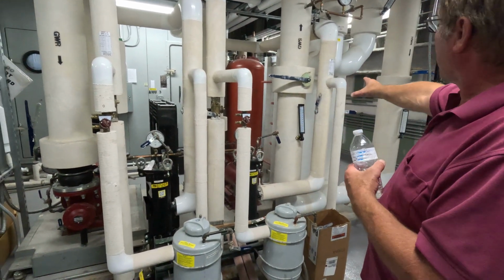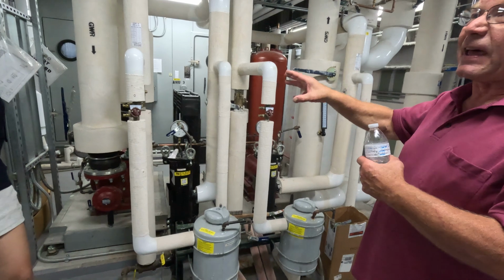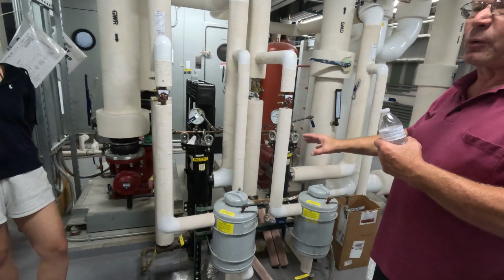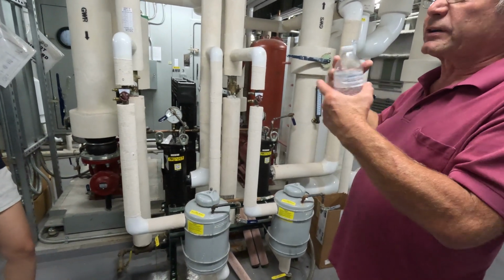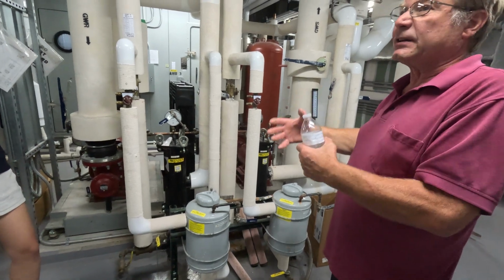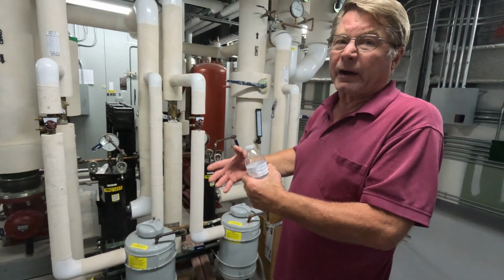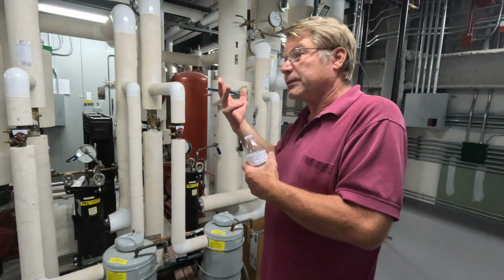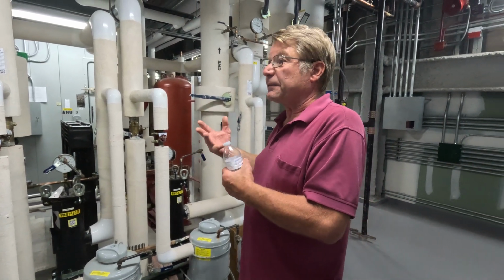These pumps here go through a plate exchanger and actually take that heat and take it down to the basement where we were before, and that's what works with the reheat coils, again, to save us having to heat up more water. So again, this energy is being used 3 times. So there's your energy efficiency.